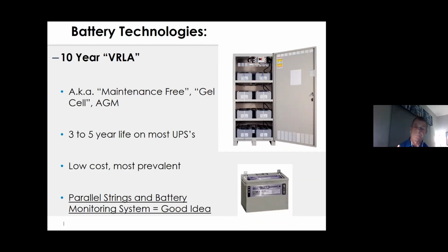But even if you didn't use them at all, they'd last 10 years. With regular maintenance and paying attention to the life of the batteries, keeping them in an air-conditioned room, they're going to last about 3 to 5 years, maybe 6 or 7 if you get lucky. But typically, for most UPSs, you're going to get 3 to 5 years out of those.